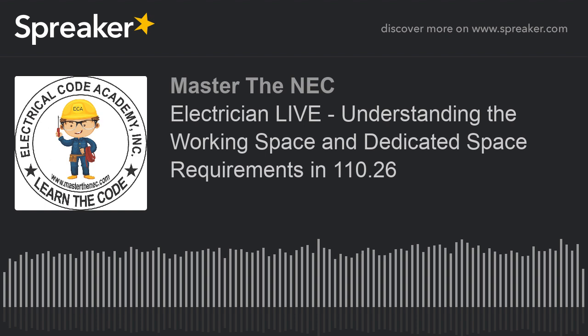Here's what it says. Illumination shall be provided for all working spaces about service equipment, switchboards, switchgear, panelboards, or motor control centers installed indoors. Now, let me define this a little bit more. It talks about service equipment. It talks about switchboards. It doesn't say service equipment such as. It says service equipment in general. Then when it talks about switchboards, switchgear, and panelboards, they may be feeder panelboards. They may be feeder switchgear. They may be feeder switchboards. So I have people that read this and say it's only the service equipment when it comes to switchboard, switchgear, and panelboard.